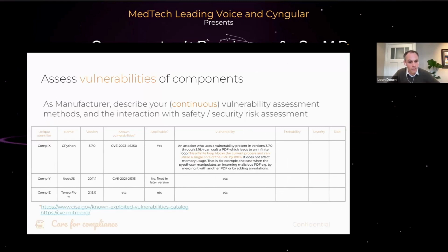So for example, the CVE database from MITRE today, I found really useful. It's a little bit more extensive than the one that the FDA refers to, the CISA.gov one. And then you will find that, for example, for this specific version of Python, there is a known vulnerability, and you need to assess, is that vulnerability applicable to my device? In this case, for example, yes. And it gives an attacker, in this specific example, the option to create infinite feedback loops, which would block the current process and can utilize a single core of CPU by 100%, meaning that it would no longer be available to do any other type of activities.